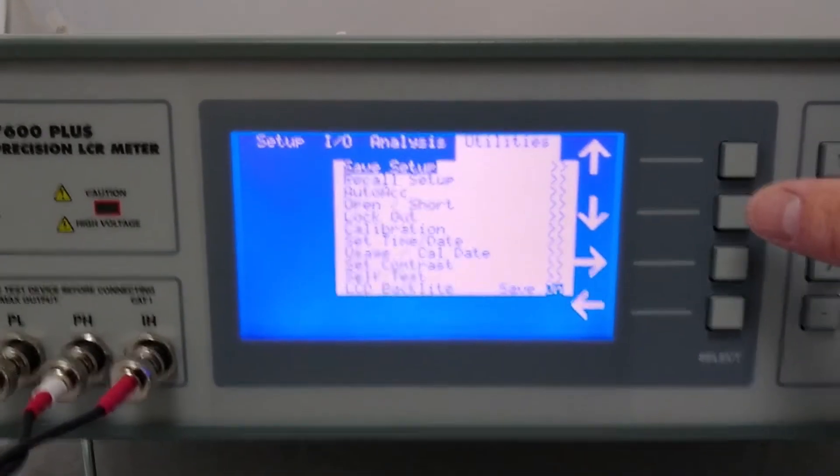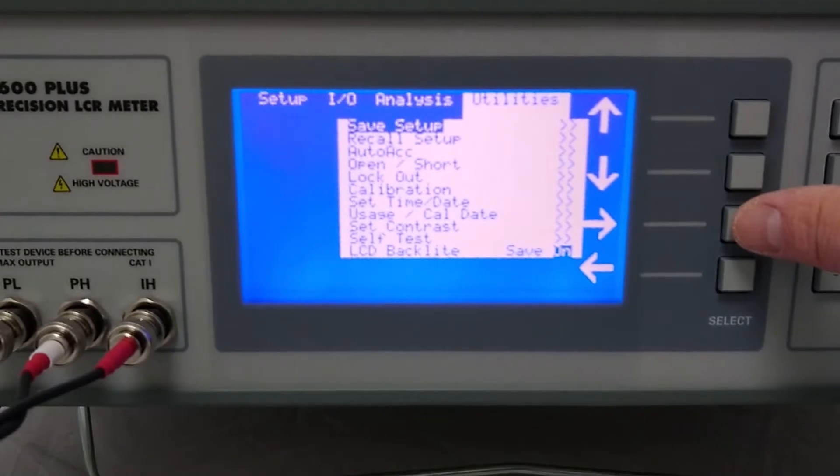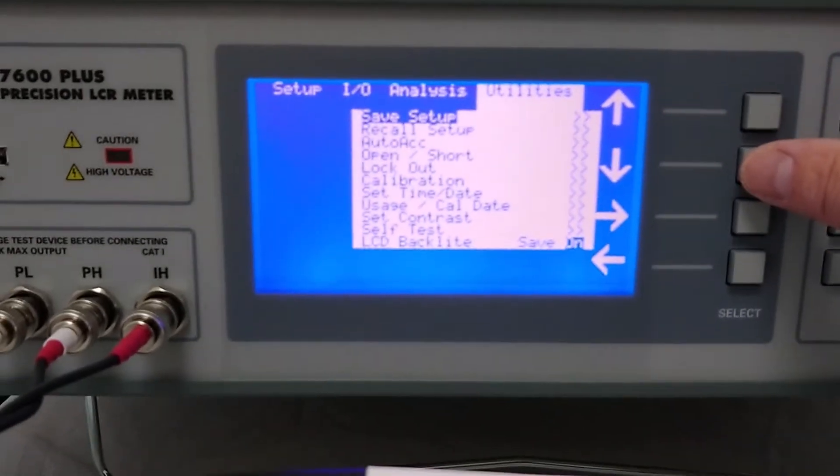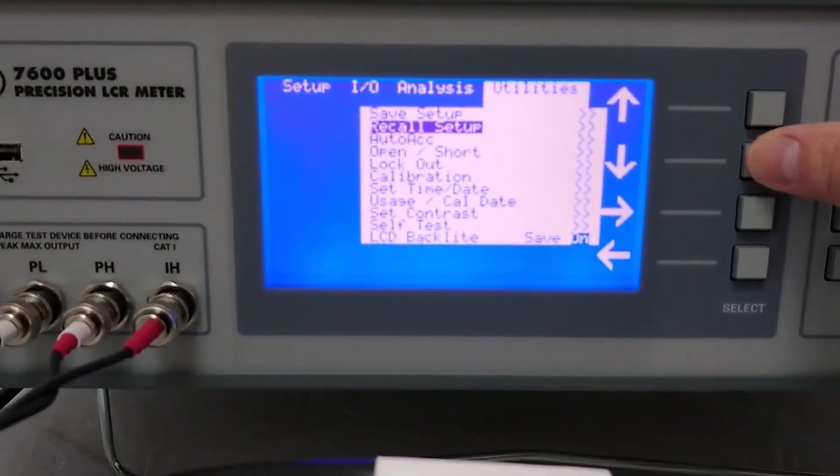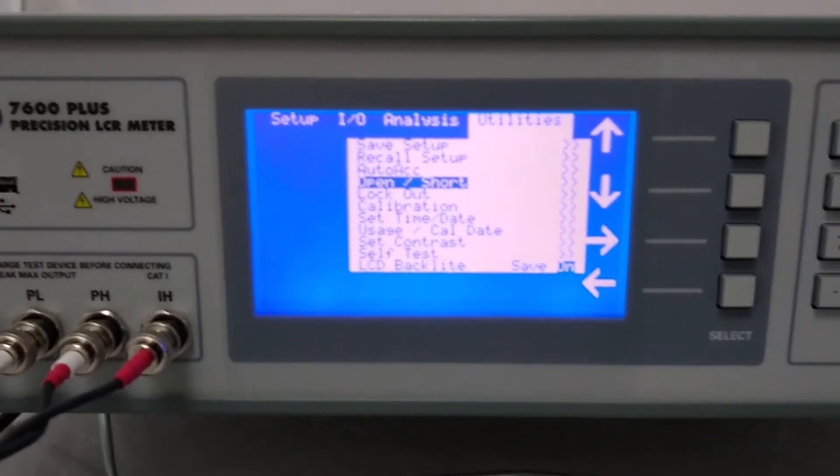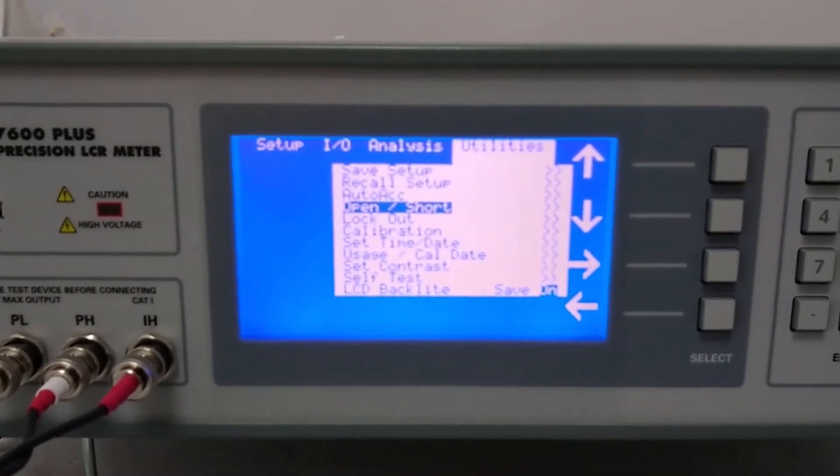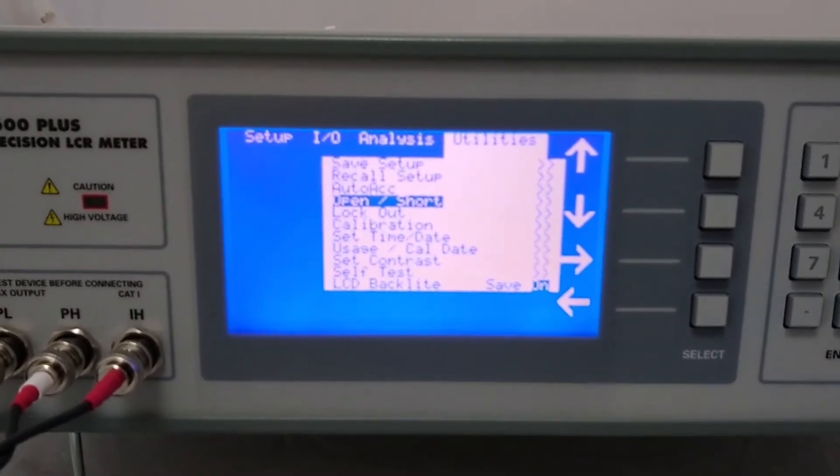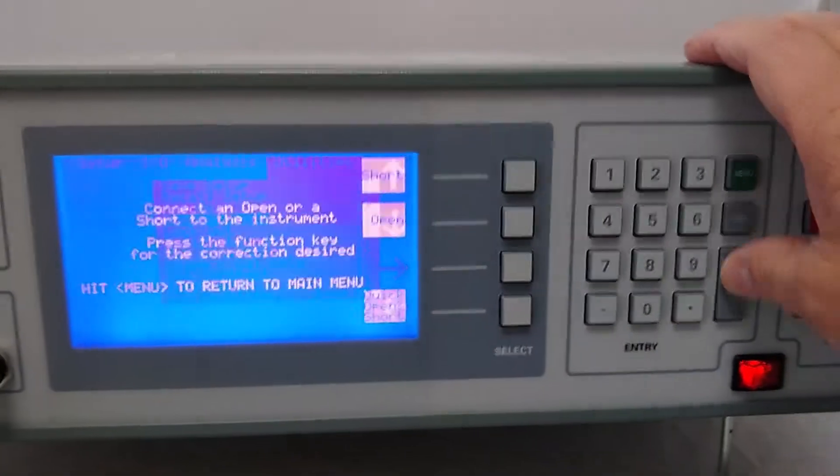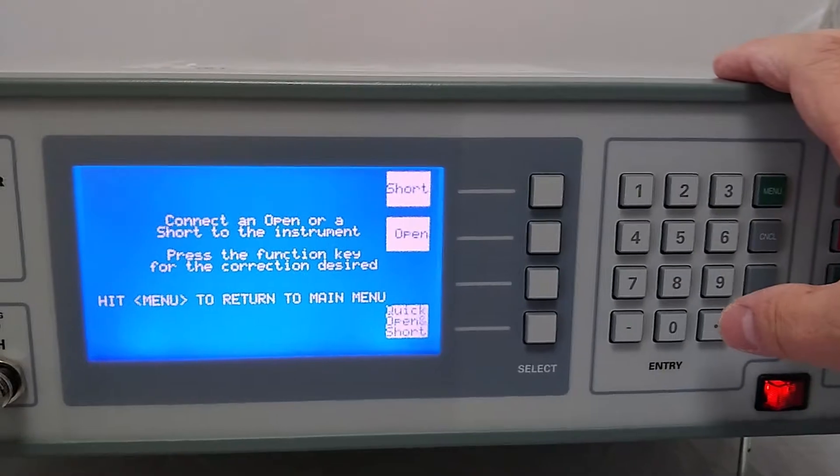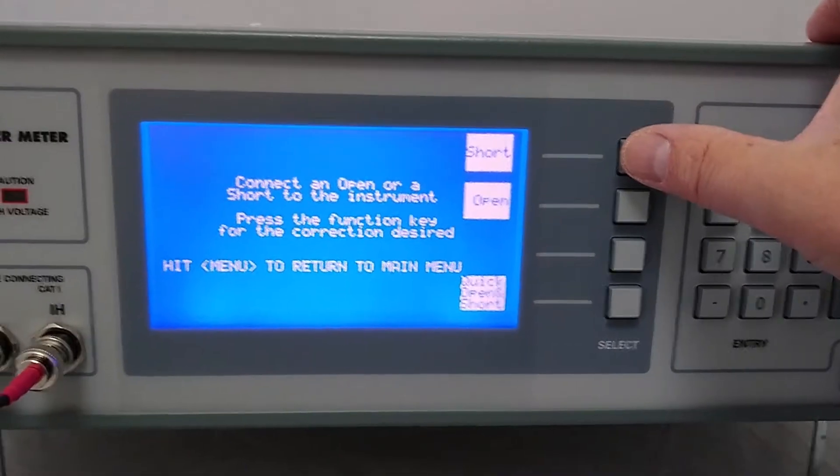This way every time we power the unit on, it will come back to the setup that we want to do. The next step that we're actually going to do is configure the cell to do opens and shorts because we've got to compensate for the cables and the adapters that we have attached to the cell. So we press enter on the open and short. And the first thing we want to do is a short.